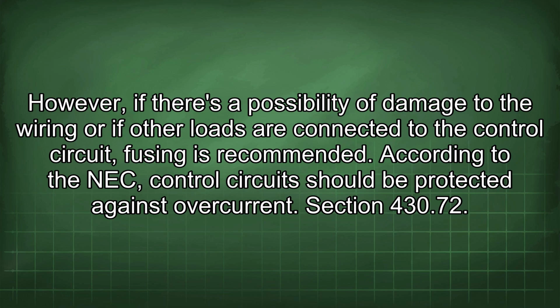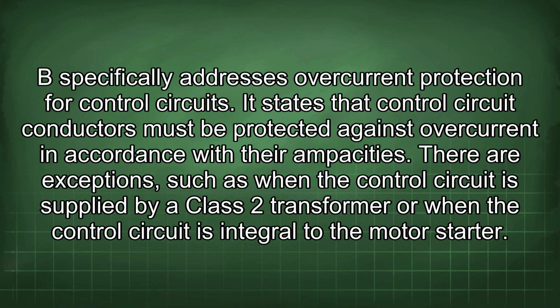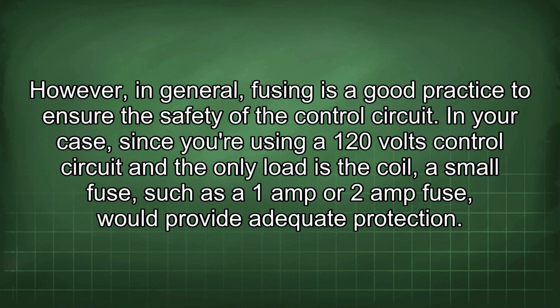Section 430.72(B) specifically addresses overcurrent protection for control circuits. It states that control circuit conductors must be protected against overcurrent in accordance with their ampacities. There are exceptions, such as when the control circuit is supplied by a Class 2 transformer or when a control circuit is integral to the motor starter. However, in general, fusing is a good practice to ensure the safety of the control circuit.